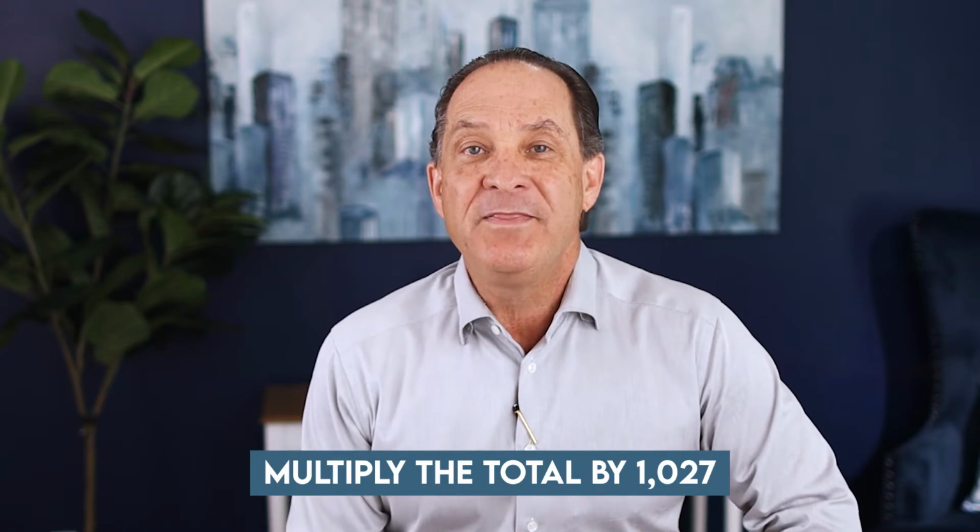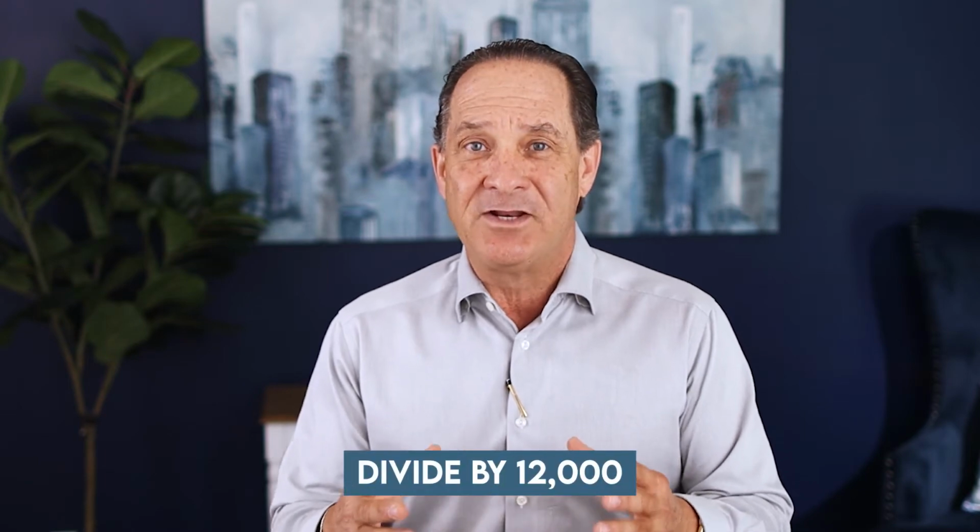Once you have that total, you're going to want to multiply that by 1,027, and that will give you the number of British thermal units that you have. Now the 3 words British thermal units may not sound very familiar to you, but when you say their initials, it will. It'll tell you how many BTUs you're dealing with. And I think we've all heard the term BTUs. Once you have the number of BTUs, you'll want to divide that number by 12,000. And that will give you the number of tons that you need to install to operate that space efficiently and effectively.